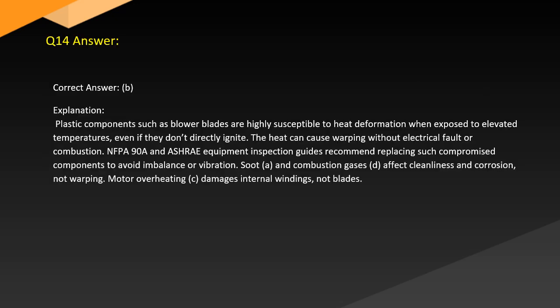Answer. Correct answer: B. Explanation: Plastic components such as blower blades are highly susceptible to heat deformation when exposed to elevated temperatures. Even if they don't directly ignite, the heat can cause warping without electrical fault or combustion. NFPA and ASHRAE equipment inspection guides recommend replacing such compromised components to avoid imbalance or vibration. Combustion gases, D, affect cleanliness and corrosion, not warping. Motor overheating, C, damages internal windings, not blades.